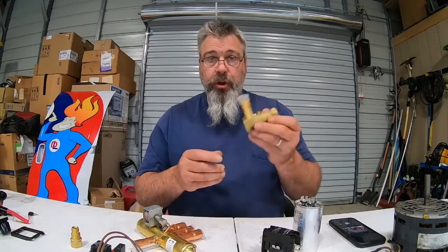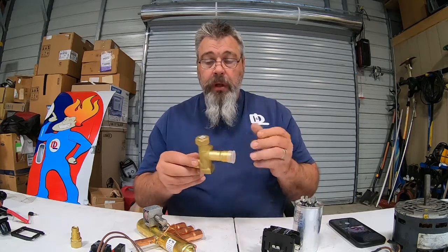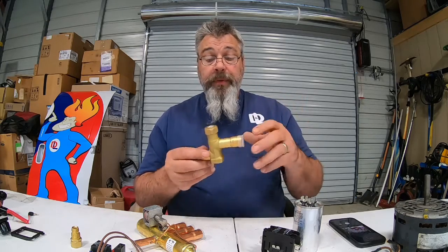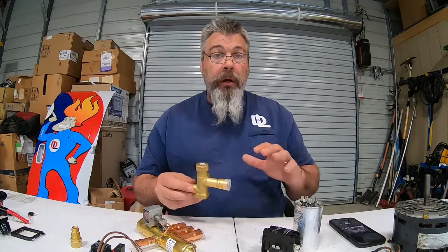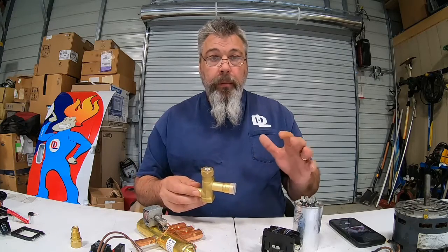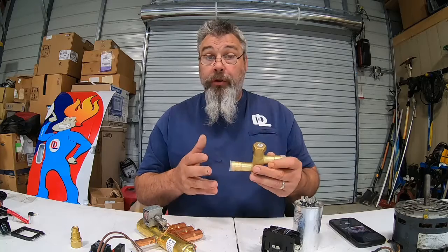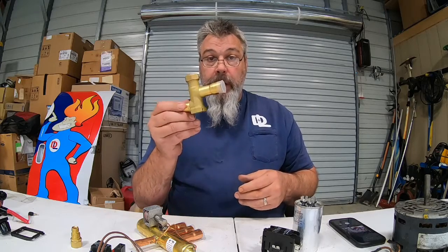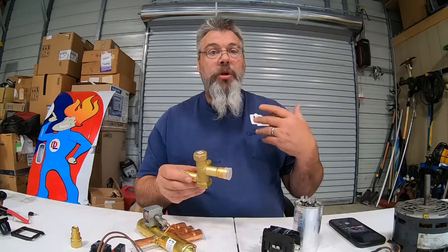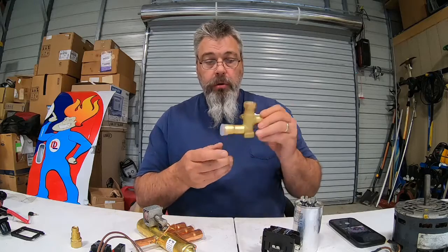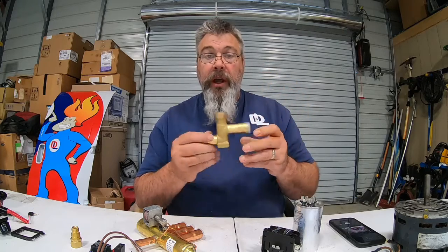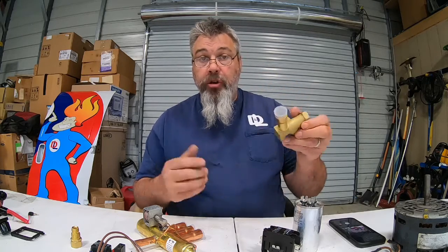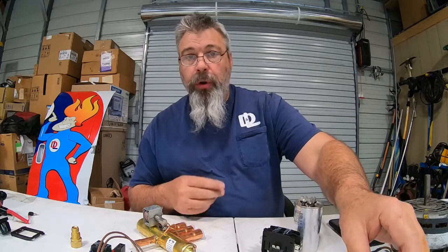Okay, so two of these: suction service valve and discharge. Summertime, this one will be cold. The small one will be hot, warm. In the wintertime, this becomes hot and your discharge becomes cool. So two of these: a suction service valve and a liquid line or discharge service valve. So that's two of those.